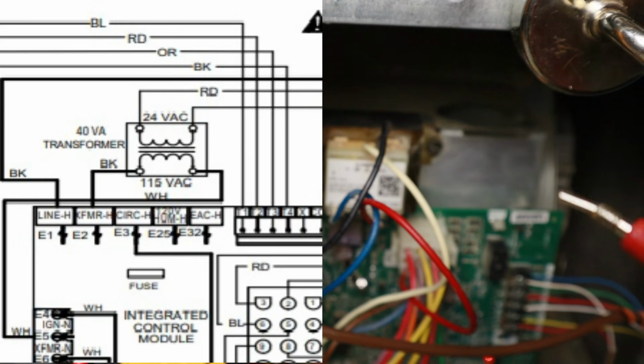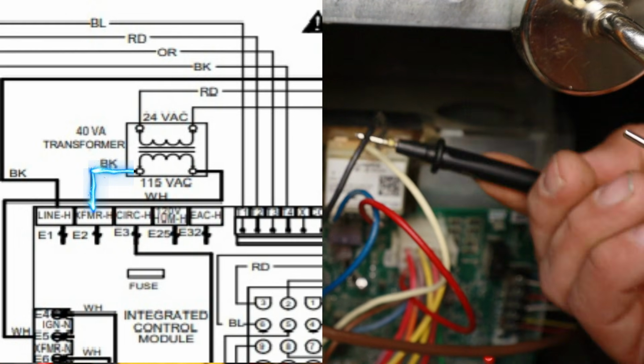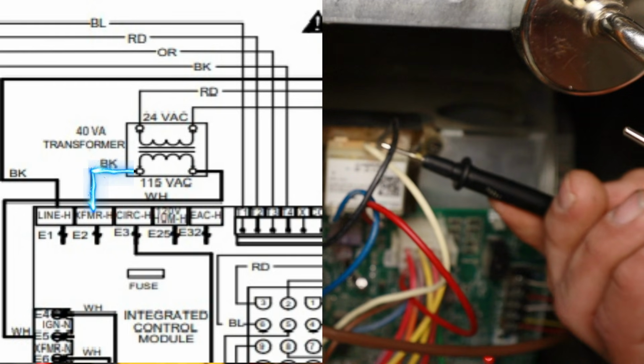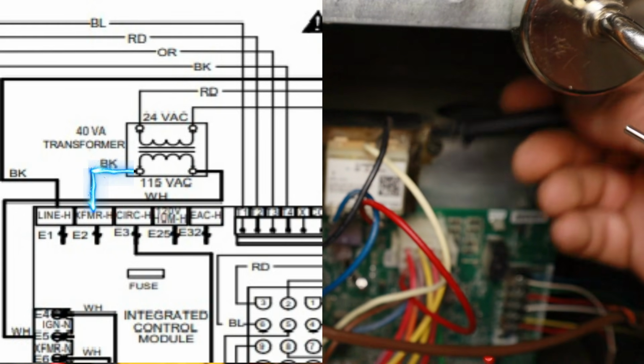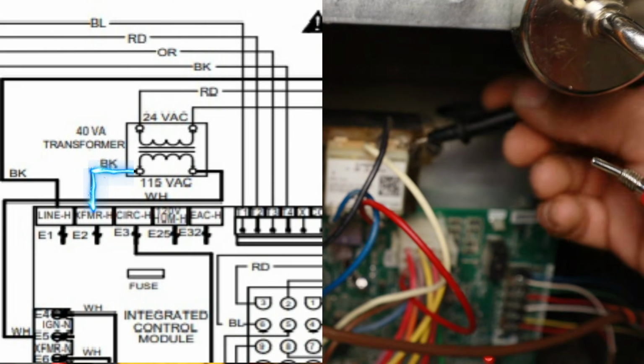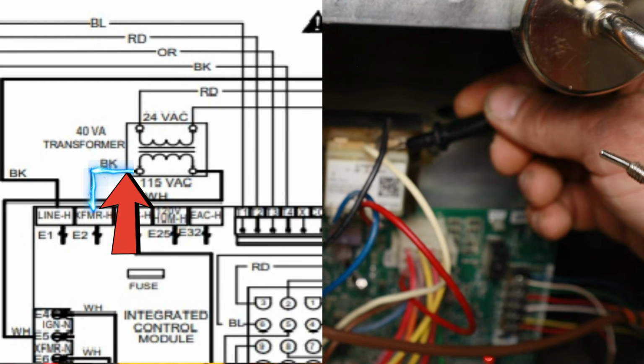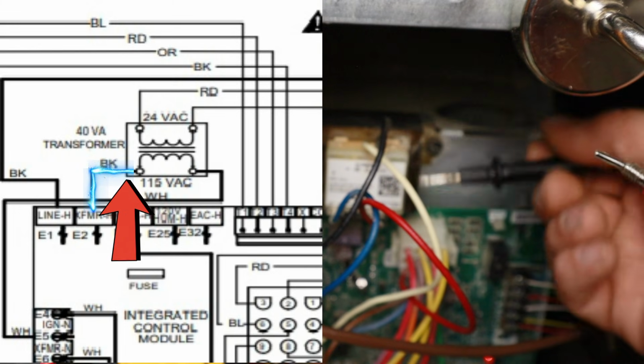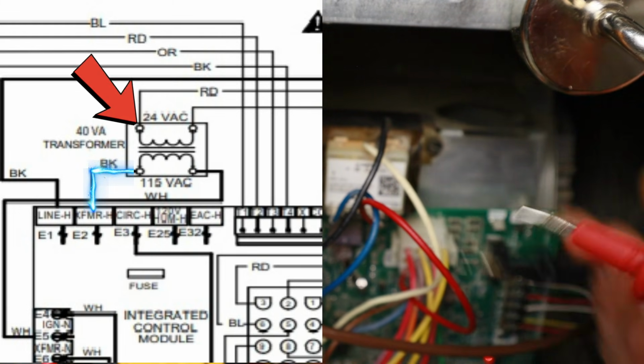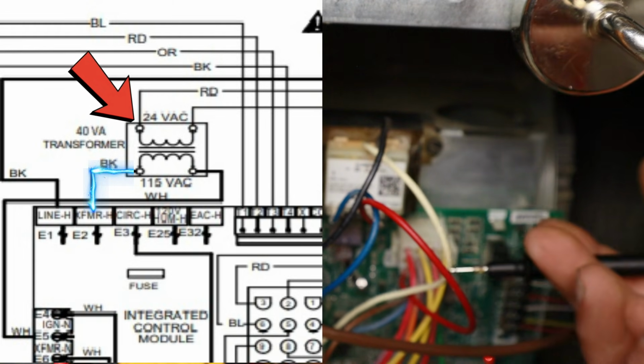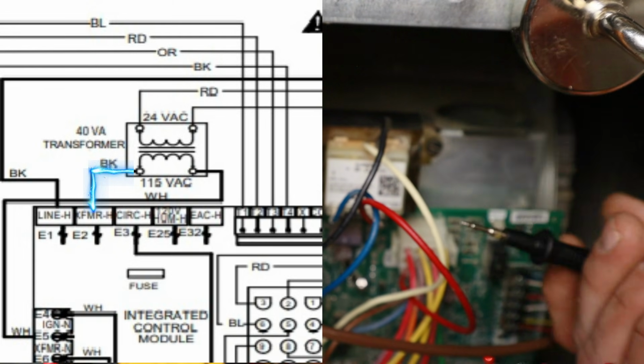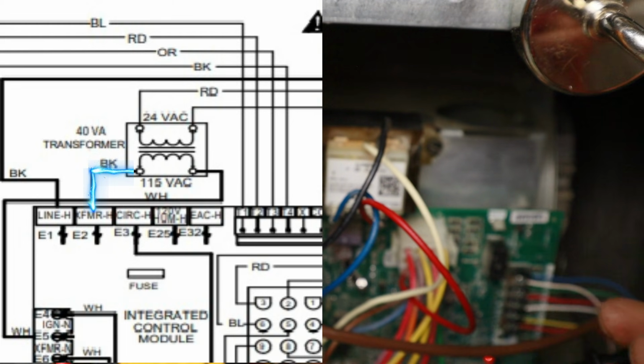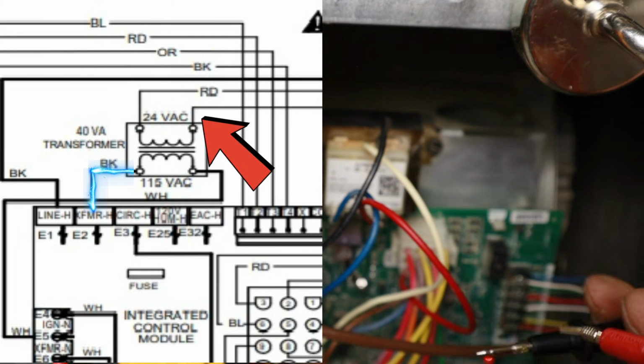So going back to our full schematic, we could see we have a black wire coming off a transformer H terminal on our control board, which we just tested. We have 124 volts coming off of that. So that is our black wire right here. We should have 124 volts coming off of transformer H into the primary side of our transformer. Now on some of these transformers you can test for the 120 right there. This one I can't, it goes inside the transformer. So what I do in these situations is I just test the low voltage coming out the other side of the transformer, because that is the whole purpose of the transformer, is to take that 120, step it down to 24.